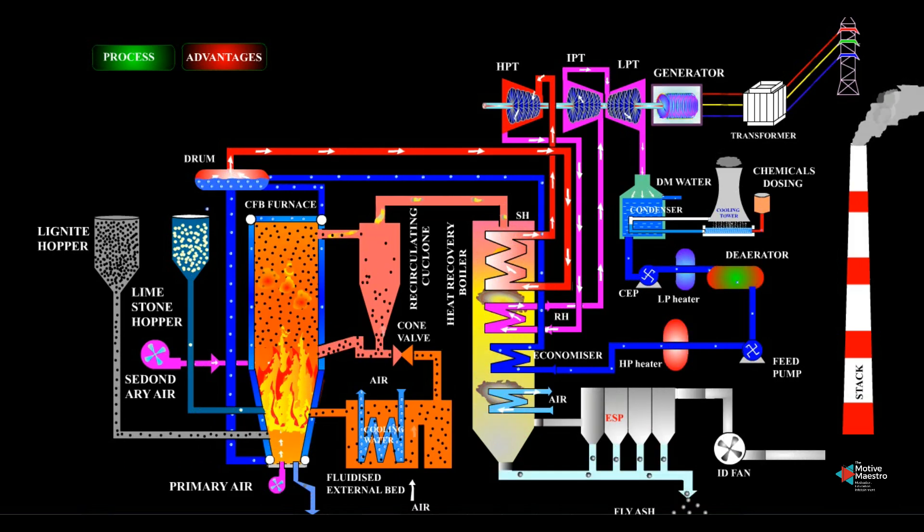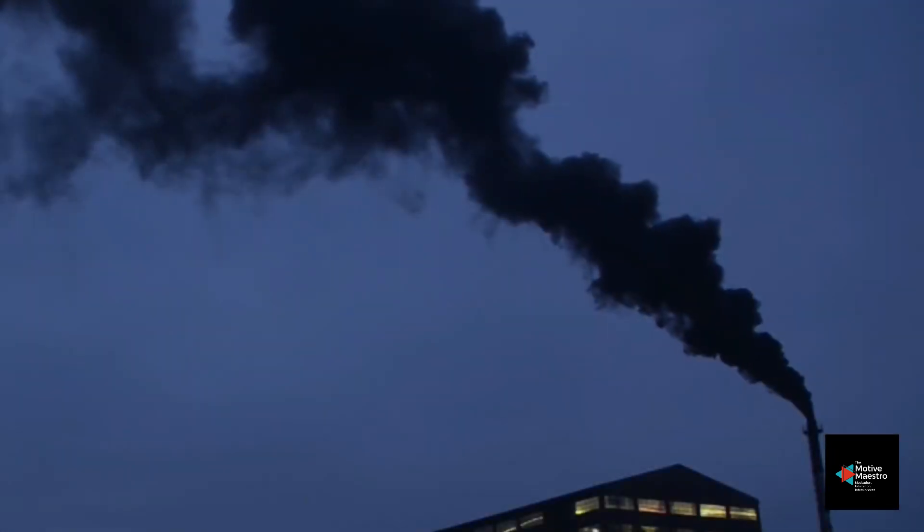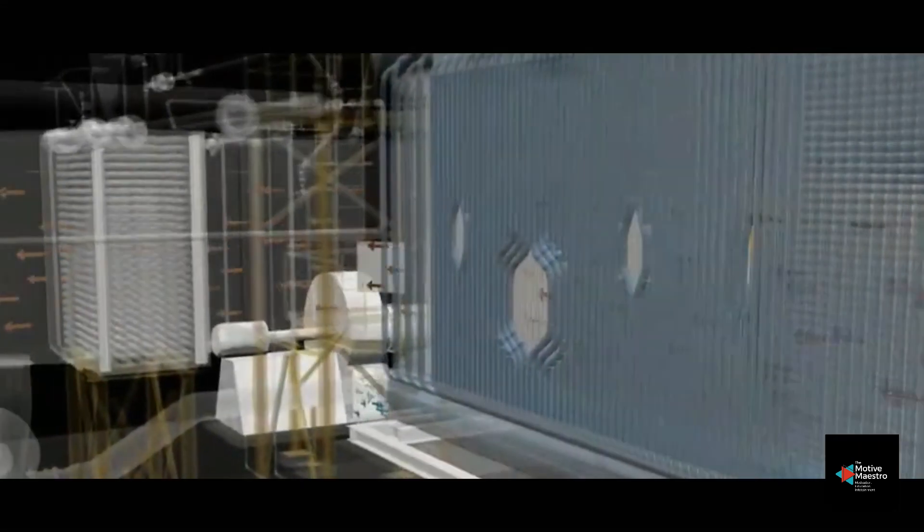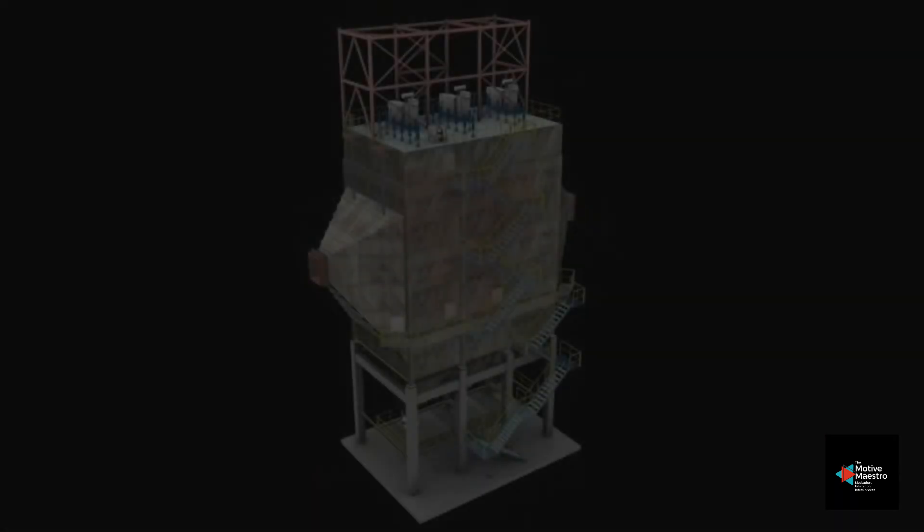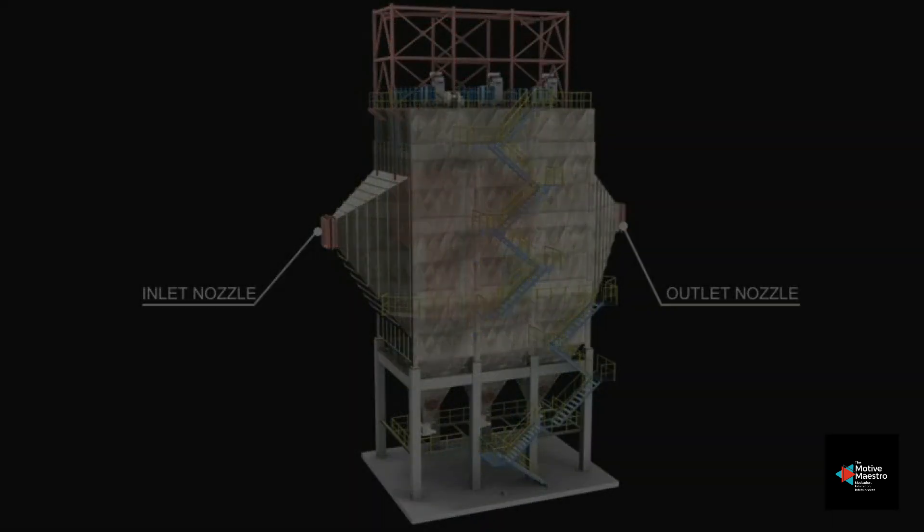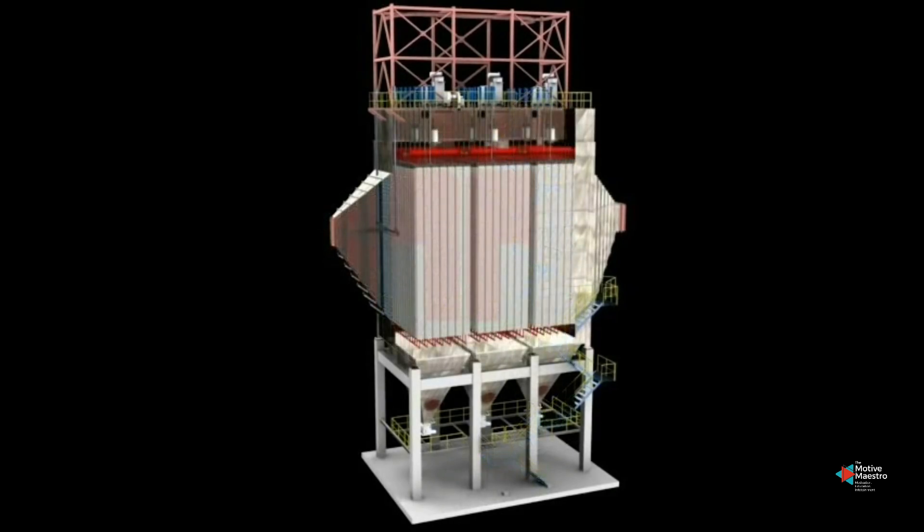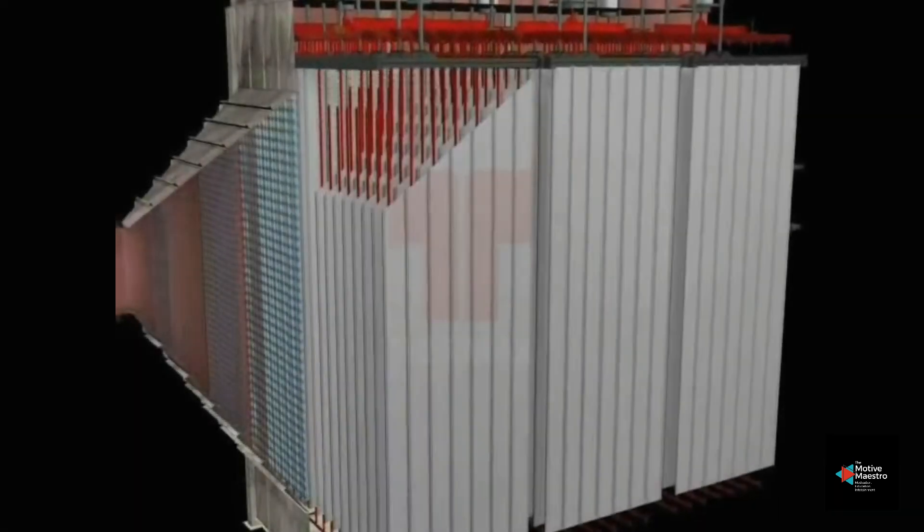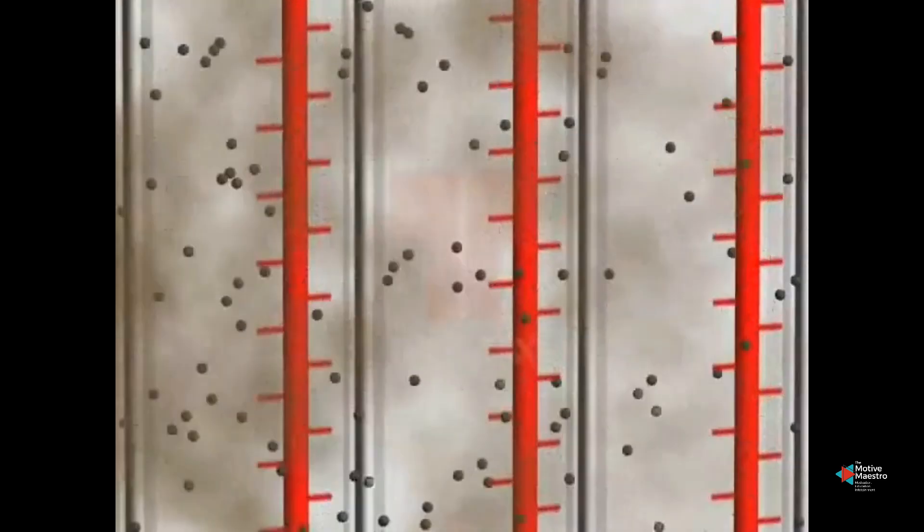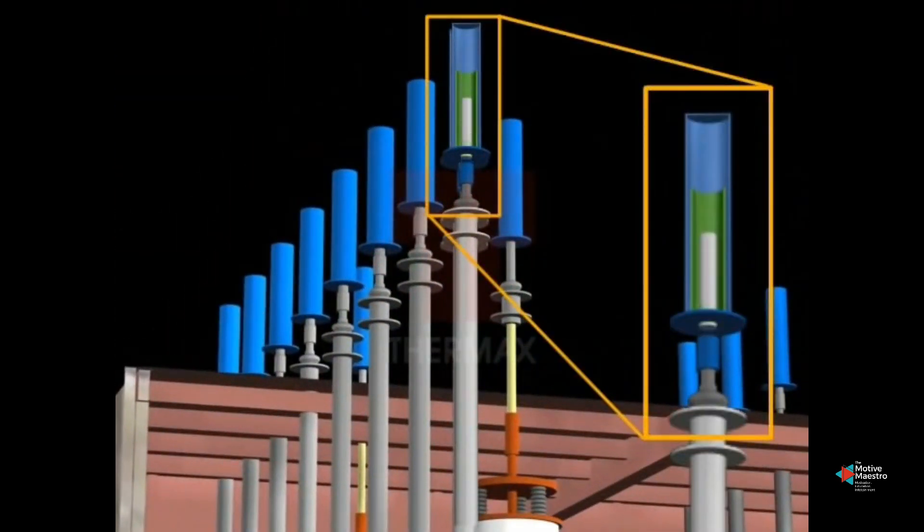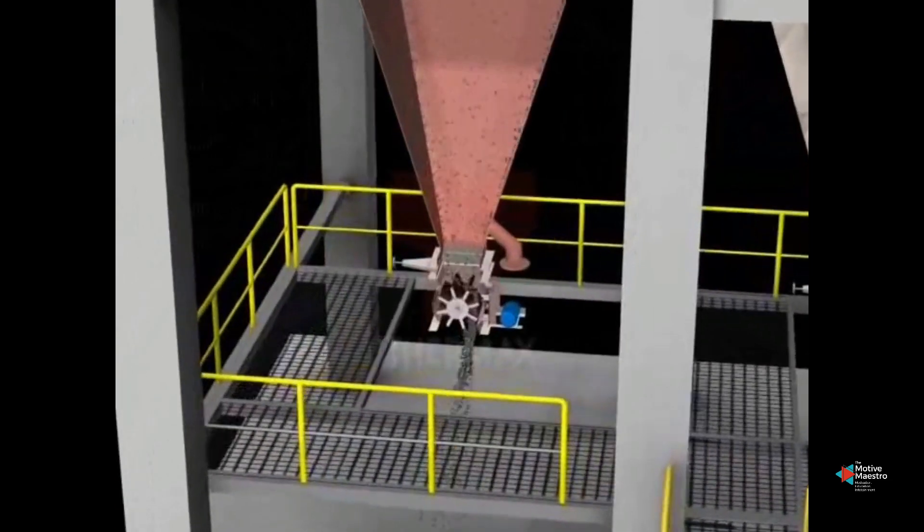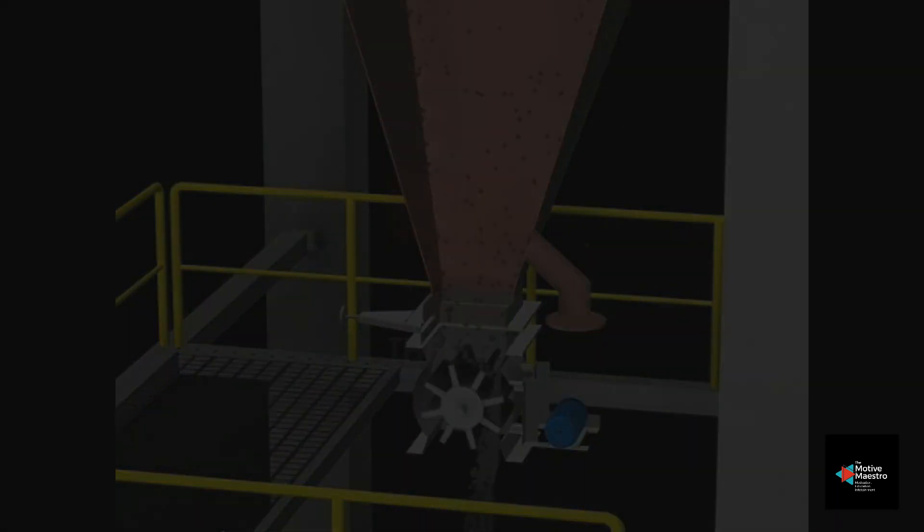Let's have a quick look now at the exhaust gas system. The exhaust gas system is also known as the flue gas system. The exhaust gases will pass through the preheater and some of the remaining heat from the exhaust gases is used to heat up the air which is being fed to the boiler. As the exhaust gases pass through an electrostatic precipitator, there it will effectively ionize the exhaust gas stream so that particles in the flue gas are attracted to large metal plates. These metal plates have a large contact surface area. Particles in the exhaust gas stream such as fly ash will be attracted to these large surfaces. And in this way we can remove them from the exhaust gas stream. Periodically these large plates will become totally covered by such particles. Then we will simply bang them in order that the particles fall off the plates and then go to a silo where they can be discharged and disposed.